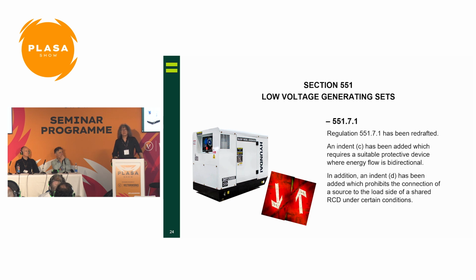There was one death in Australia because when the source is on the wrong side of a unidirectional device - let's say an RCD - and the RCD operates, the source can burn out the innards of the RCD, the coil and the control equipment within. When you reset it, you think it's working again, but the device has often been fried and is no longer operable, and will not save a person's life. So what's being said here is that the device has got to be bidirectional - suitable for a source that can go on both sides of that device.